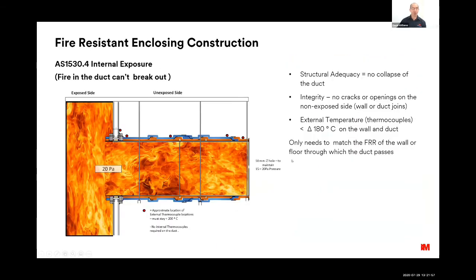So I did touch on AS 1530.4 and alluded to the configurations for ducts. For ductwork, there are some configurations that need to be tested. One of them is testing for internal exposure, where fire breaks into the duct. We're making sure in the test that fire doesn't break out. Again, we're measuring the structural adequacy and the integrity, so that there are no cracks or fire breaks out of the duct into the non-affected compartment, and also we're interested in the insulation, so that if there are any combustibles nearby, they're not ignited.